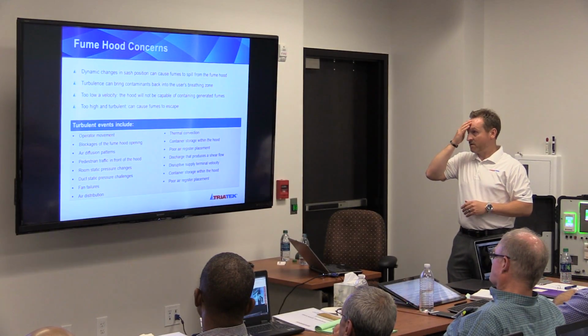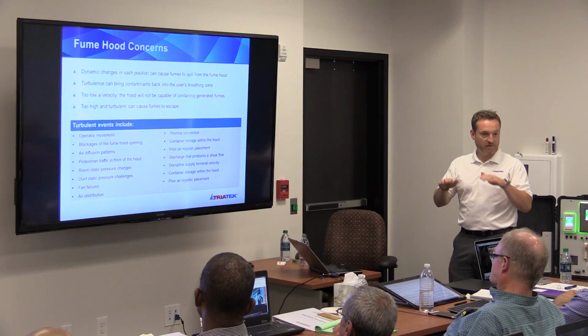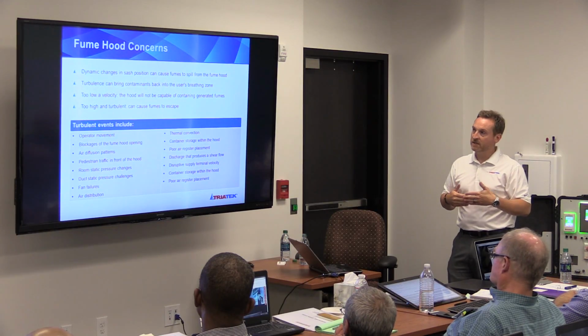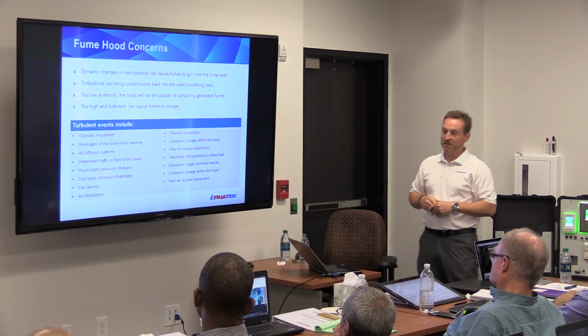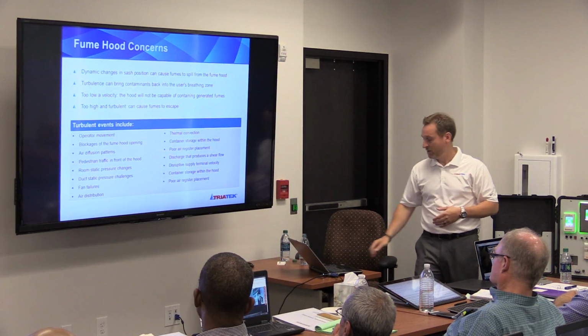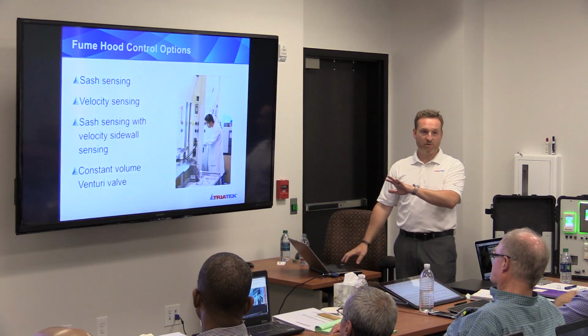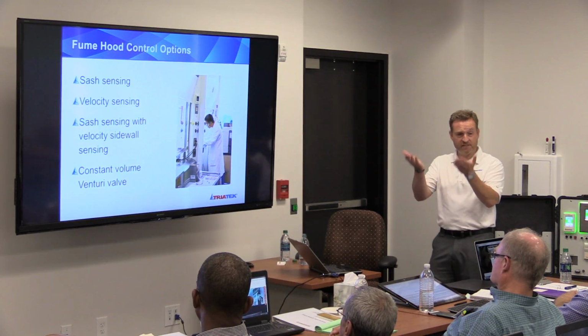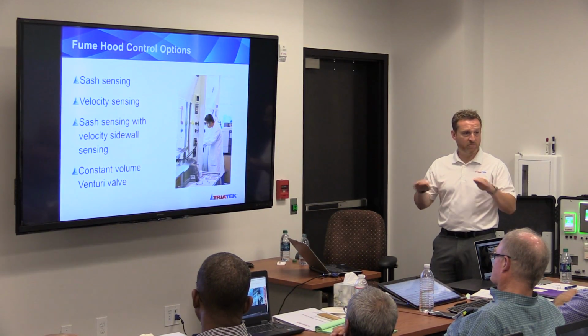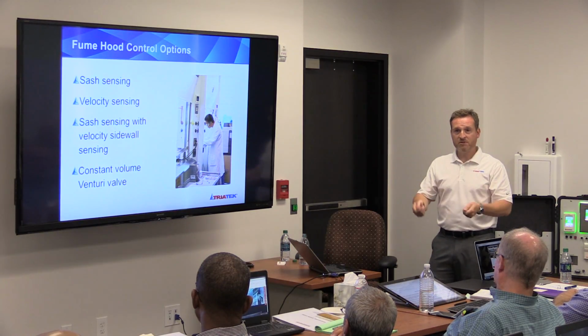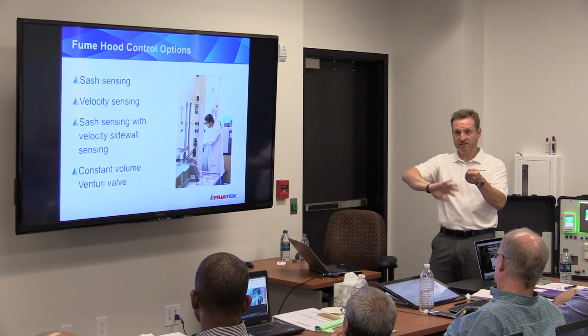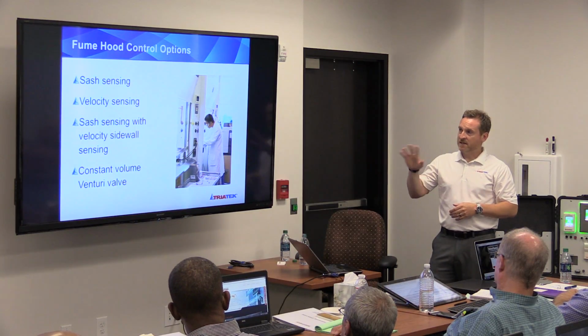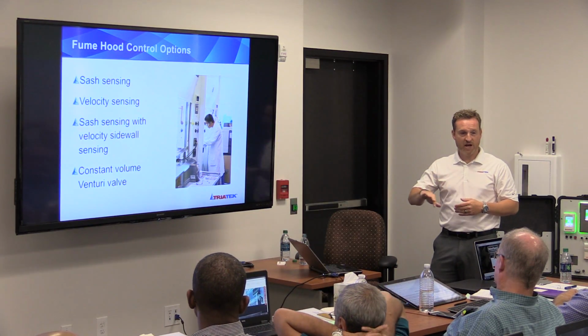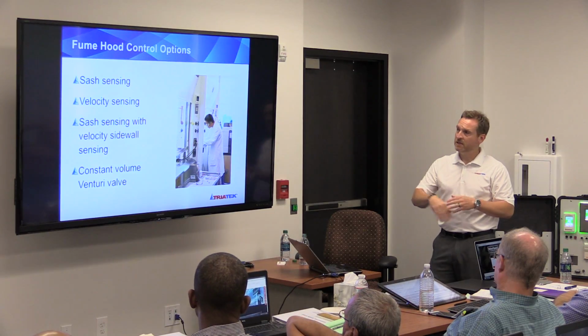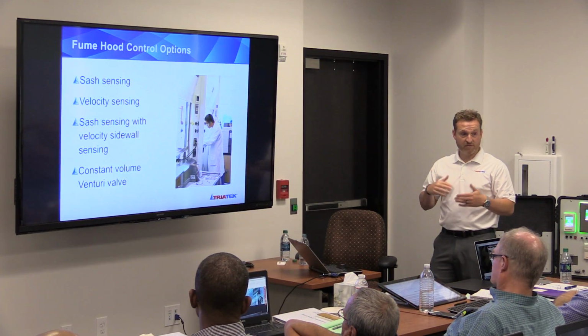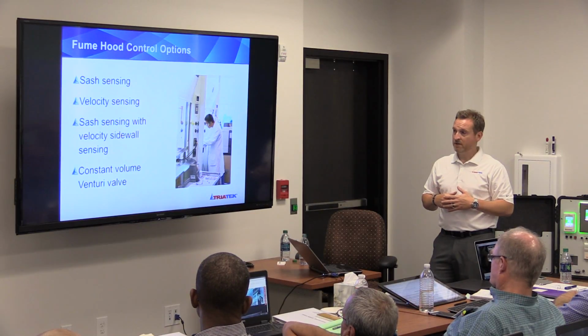We'll start with fume hood concerns. Dynamic changes can cause fumes to spill from a fume hood. Okay. Too high or too low of a velocity could cause fumes to spill from a fume hood. And then we'll get into the options of how we would control them, right? Based on sash sensing. Is everyone familiar with the fume hood and how it works? Basically, you have a sash that opens and closes. We're going to maintain a face velocity at that hood at all times. Sash sensing would be an option. Actual velocity sensing, where we're measuring the flow through the hood. A combination of both sash and velocity sensing. We'll get into that control momentarily.